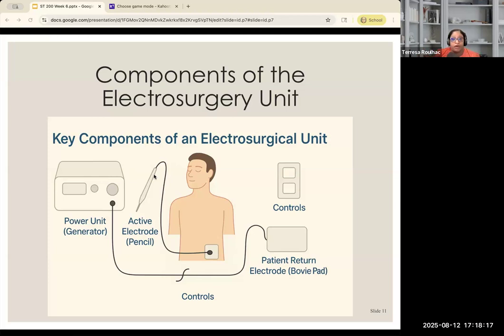Now, the generator itself, this piece over here, creates that high frequency current used in surgery. This is what sends the current to the active electrode. Whenever you hear me talk about the active electrode, think of the instrument that's going to be used on the patient, again, for cutting, coagulating, whatever the need is at that time. Your pencil, in this case, is the instrument the surgeon uses to deliver that current to the tissue. Again, it cuts, coagulates, or even vaporizes the tissue depending on the generator settings.